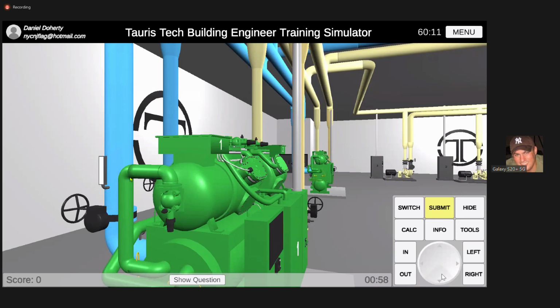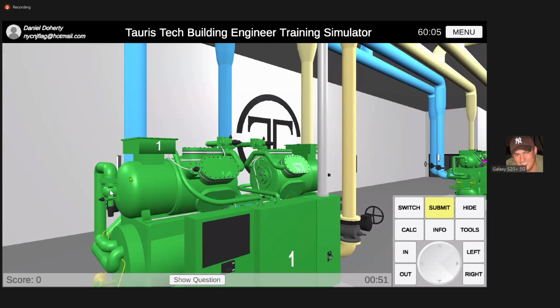Now, through your suction valve, it travels through the motor. And why does the refrigerant travel through the motor first? What does that do? Anyone know? To cool the motor down, the vapor. It cools the motor windings down. Right, it cools the windings down, okay? But listen, it's still low pressure. It's still low pressure going through here, okay?